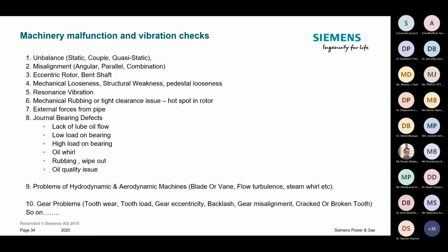It cannot start with one thing. It is possible that a system is vibrating due to multiple reasons, and when such problems come to you, you have to think of all possible reasons and address all of them. Then only will you resolve the problem. It is not possible to resolve it in one shot. Many times the vibration in the system is there because of multiple reasons, so you have to address them one by one. You have to prepare a checklist, address one issue, and if you see benefit, you keep it. If not, then address another issue.